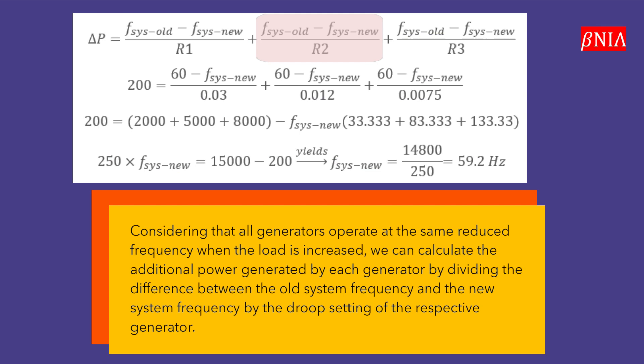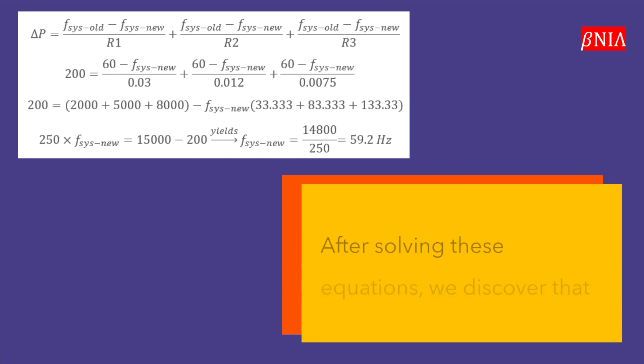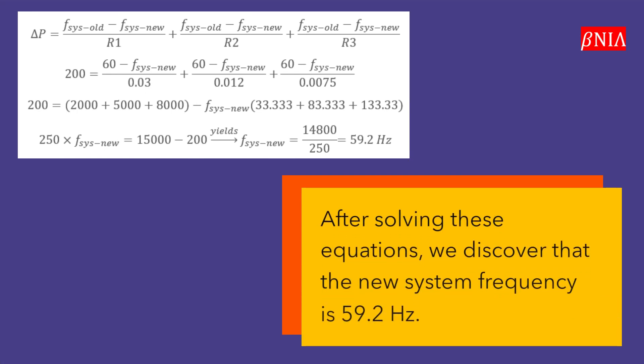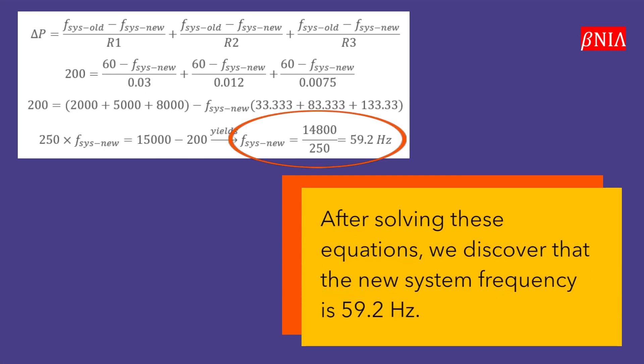We can calculate the additional power generated by each generator by dividing the difference between the old system frequency and the new system frequency by the droop setting of the respective generator. After solving these equations, we discover that the new system frequency is 59.2 Hertz.